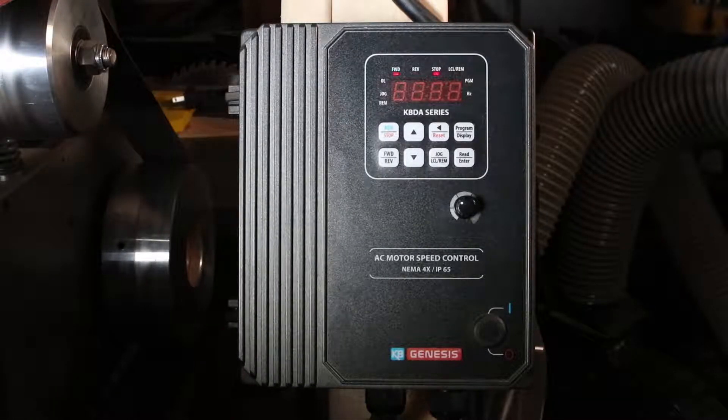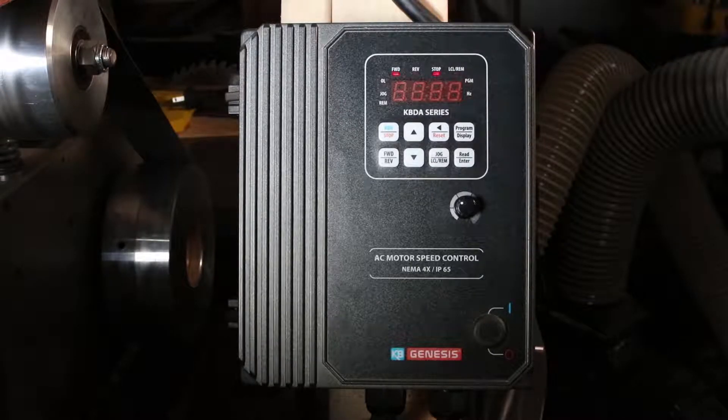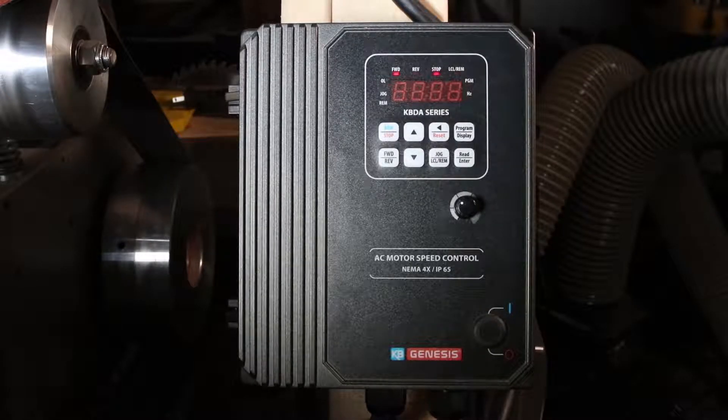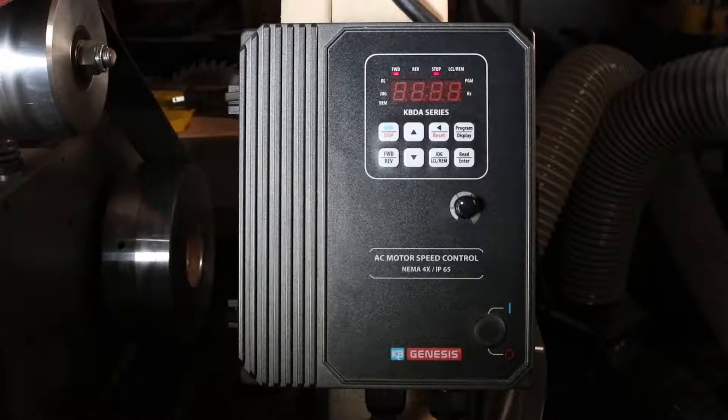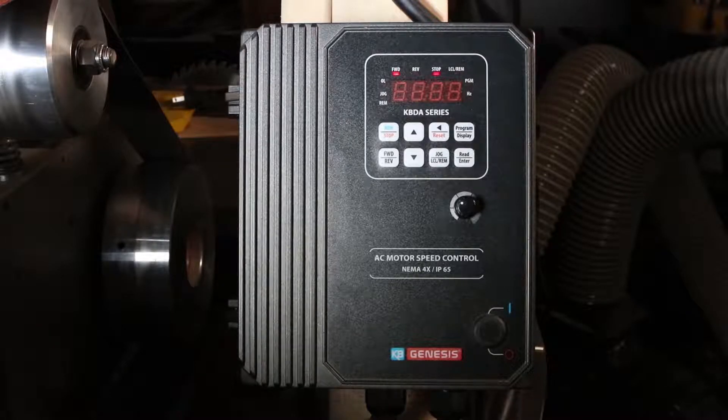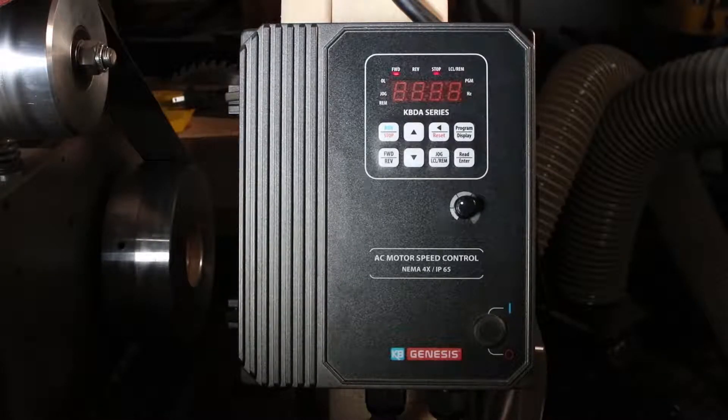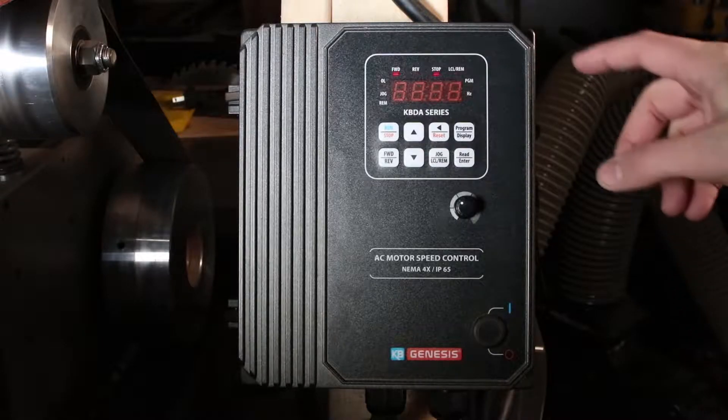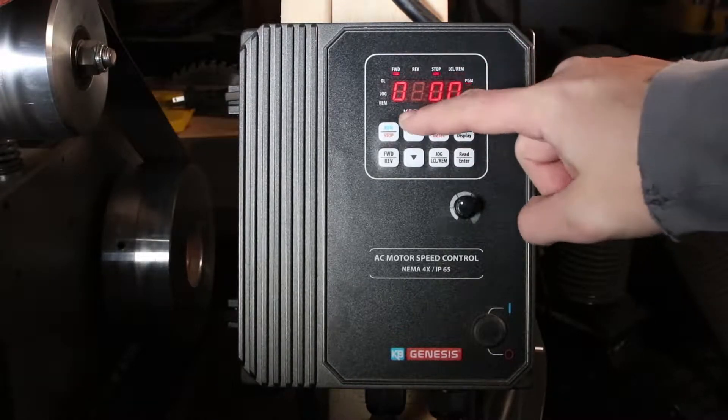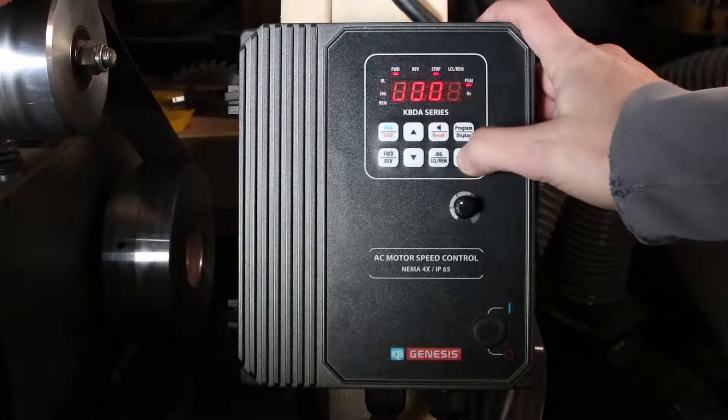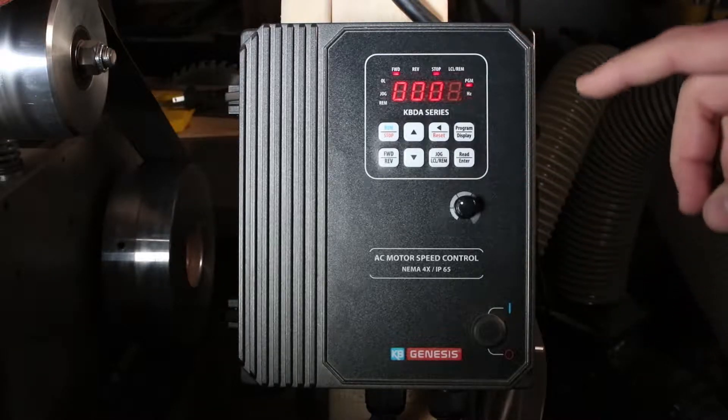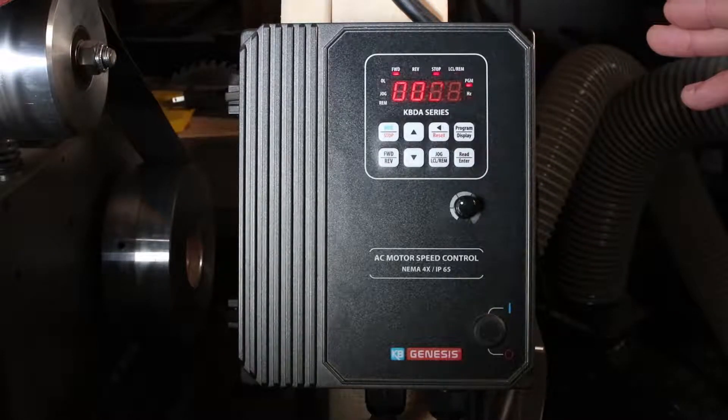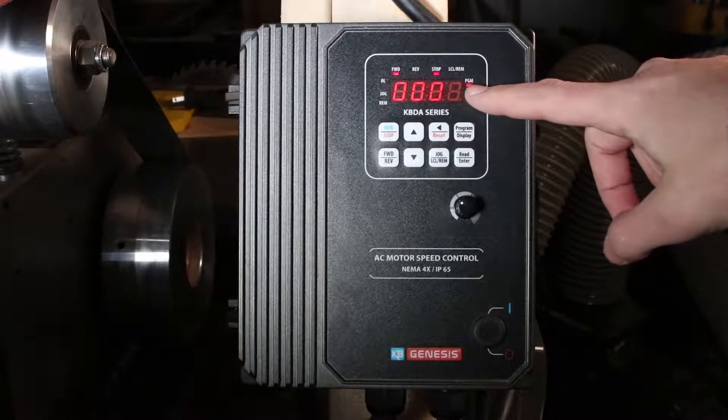So if you do have a four-pole motor and you decide to run it at double the frequency, which in the United States would be 120 Hertz, what you have to do is change option 000. So you go to program, make sure it says 000, hit enter.